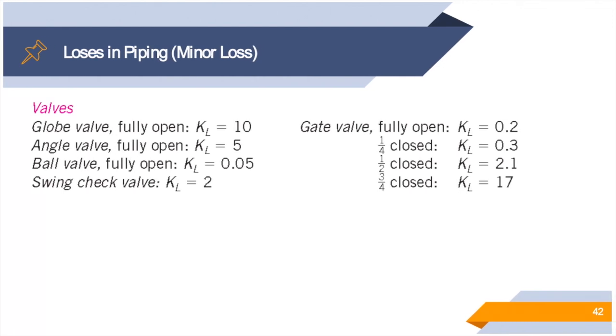For different types of valves, the globe valve has the highest loss coefficient when fully open, followed by angle valve, swing valve, and ball valve. Gate valves have a very low KL when fully open, but closing them halfway increases KL tenfold, and closing three-quarters increases it roughly 100 times compared to fully open. These are important considerations when designing piping systems.